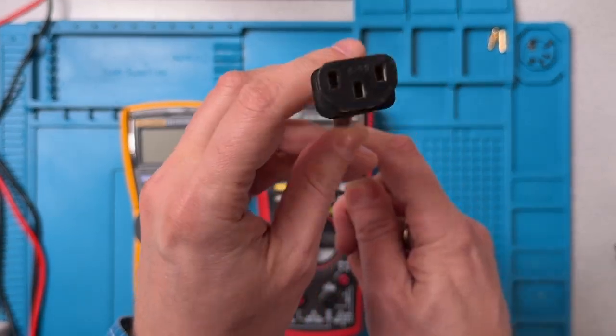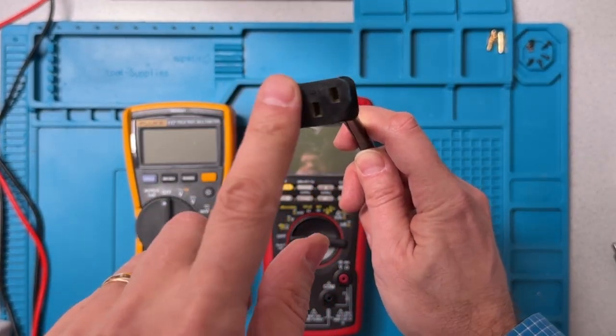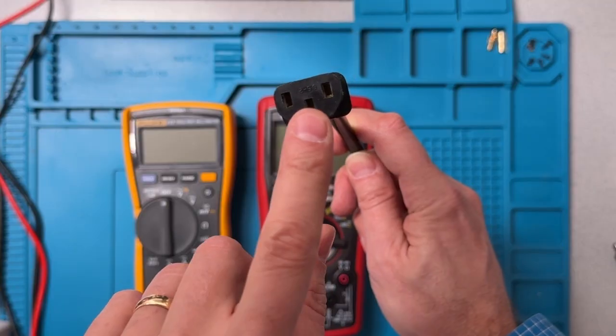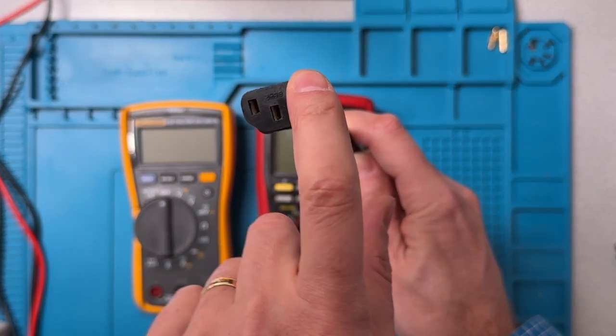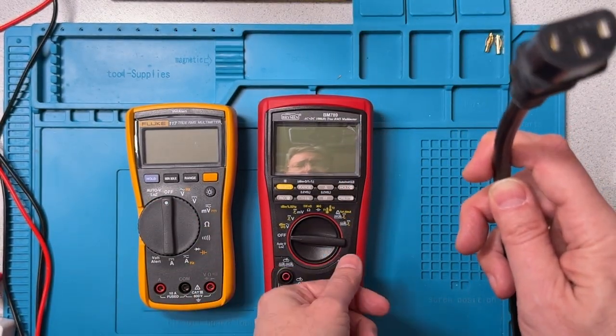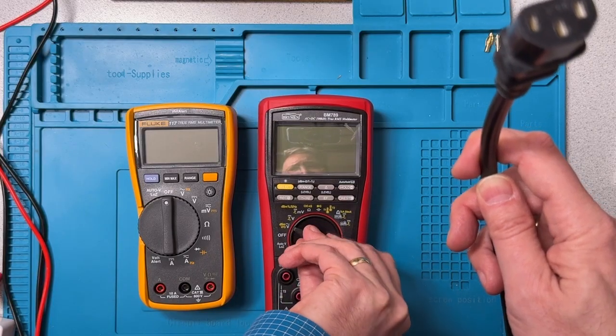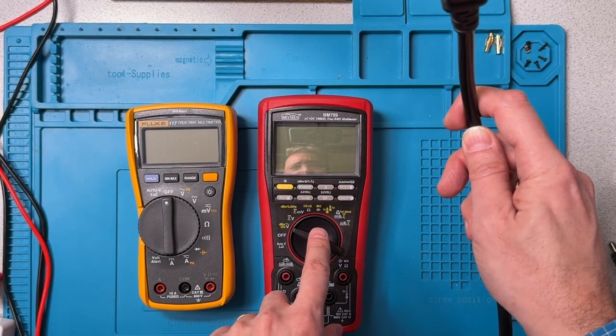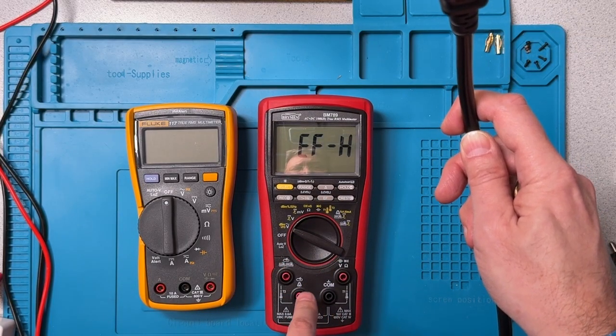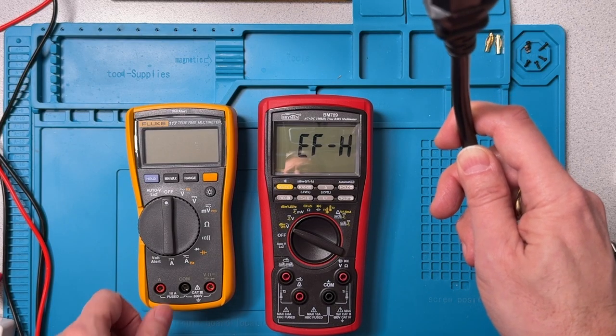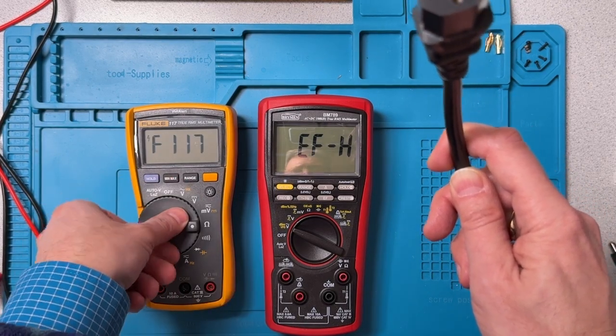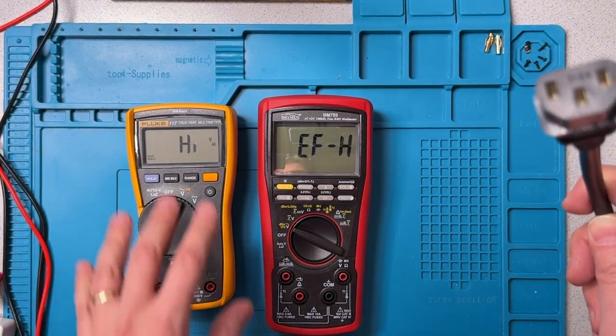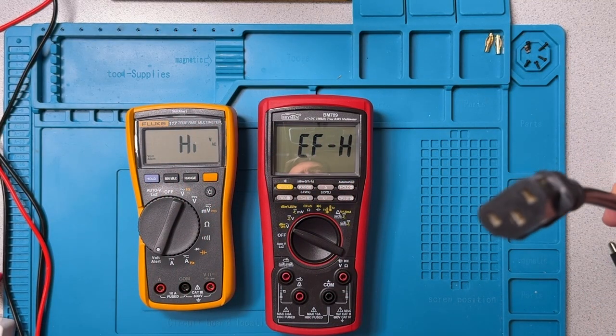Non-contact voltage, I'm going to use this wire. This is the hot line, neutral, ground and neutral over here. We're going to put the Brymen into electrical field mode. We turn it on, and this switches into the electrical field mode. And for the Fluke, we turn it down to volt alert. So they both start out in high sensitivity mode.